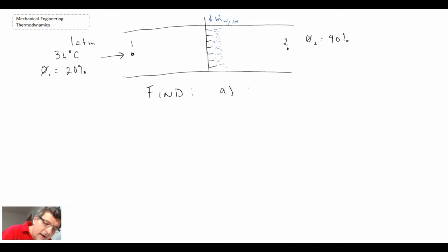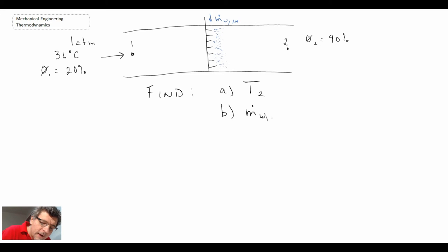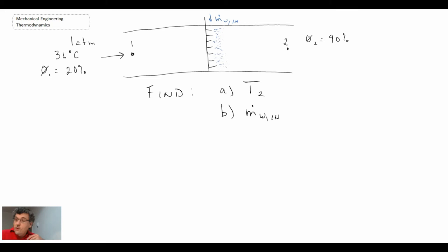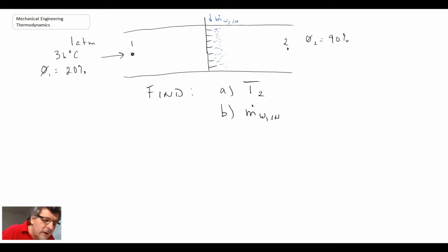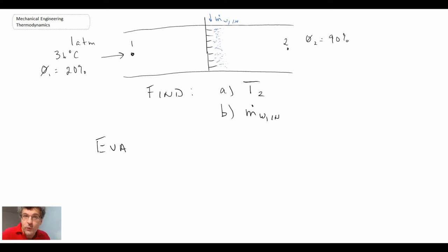We want to find T2, the exit temperature, and the mass flow rate of water being added to replenish the system. We'll solve this using the psychrometric chart. For an evaporative cooler, the enthalpy of the process is constant, so H1 equals H2.